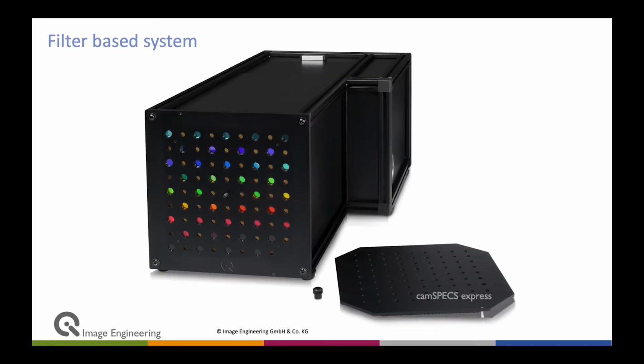A very good approach to do that is a filter-based system. What you see here is a product called camspecs Express. Basically, that's a halogen light source that back illuminates a set of 39 narrowband interference filters. That means the device under test captures an image of these filters and has then 39 measurement points. From that we can directly calculate the spectral sensitivity. So one shot and you have your spectral sensitivity.